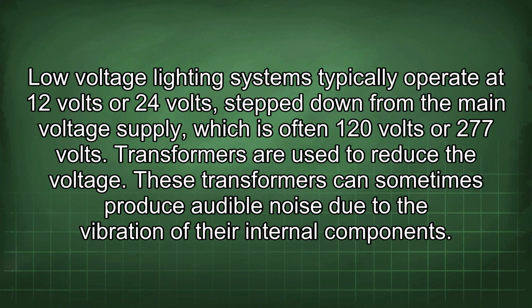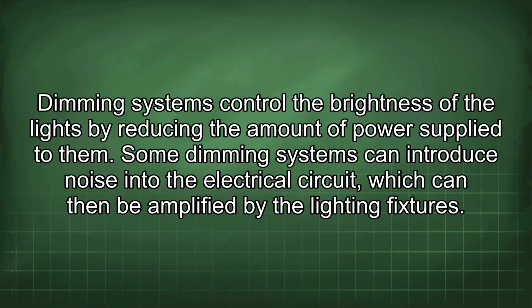Low-voltage lighting systems typically operate at 12 volts or 24 volts, stepped down from the main voltage supply, which is often 120 volts or 277 volts. Transformers are used to reduce the voltage. These transformers can sometimes produce audible noise due to the vibration of their internal components. Dimming systems control the brightness of the lights by reducing the amount of power supplied to them. Some dimming systems can introduce noise into the electrical circuit, which can then be amplified by the lighting fixtures.